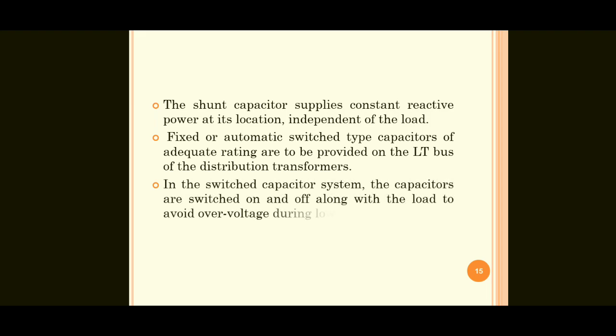Next point, fixed or automatic switched type capacitors of adequate rating are to be provided on the LT side, LT bus of the distribution transformers. Now here the capacitors are placed on the LT side. What does LT mean? Low tension. What is the primary? 11 kV, 11,000 volt to 400 volt step down. So these are placed on the LT bus. So these capacitors are placed on the secondary side of the distribution transformers. The capacitors are also fixed or automatic type.